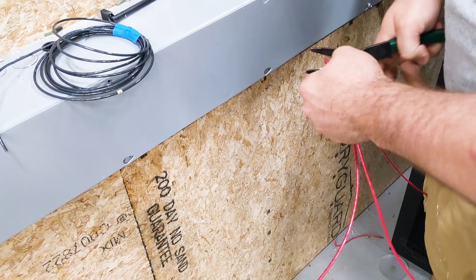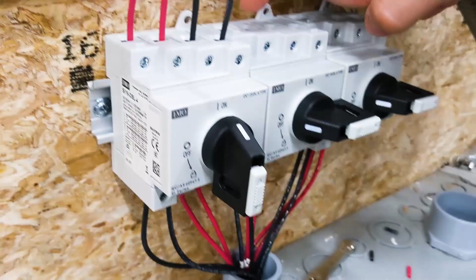There's something interesting about these disconnects that I didn't know when I first wired up the one out at the solar array, and I had to go fix it. It turns out the ports don't go straight through, they actually cross each other, like an X pattern, which I didn't know. So the port up here, called number 1, actually zigzags down here to number 2. Part of the way to tell is that it's stepped farthest back, so right here, see how this is stepped farthest back? It tags up with the one that's farthest back on the bottom.